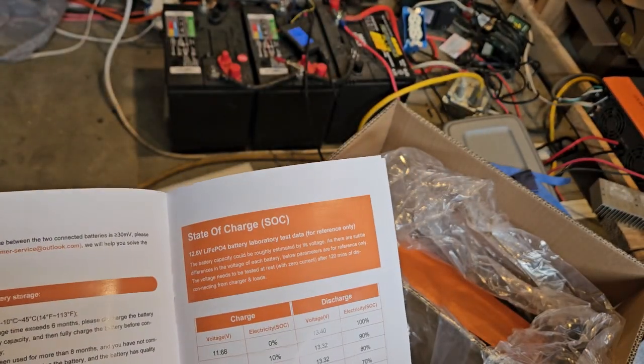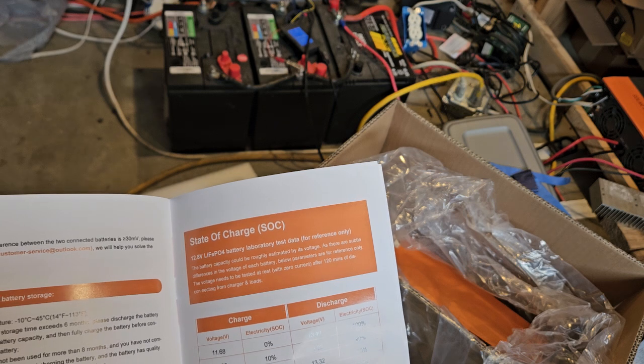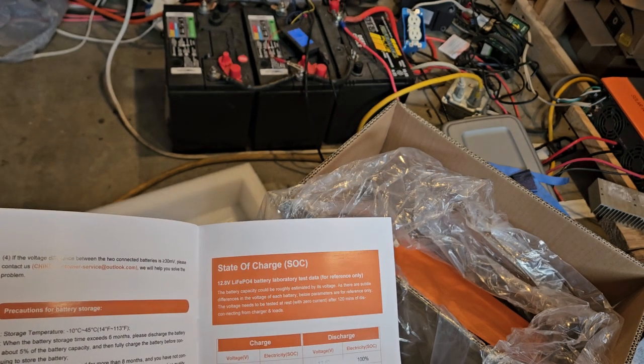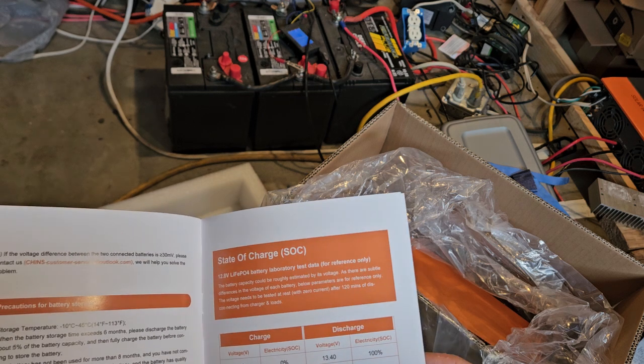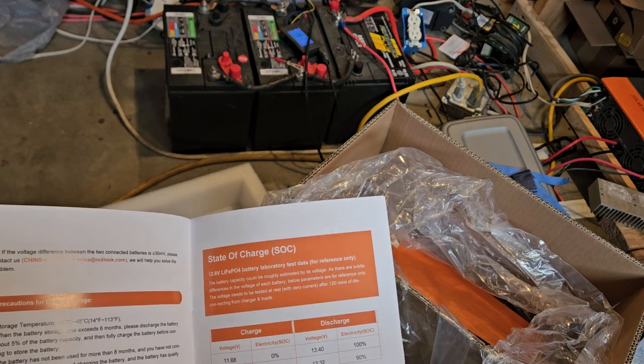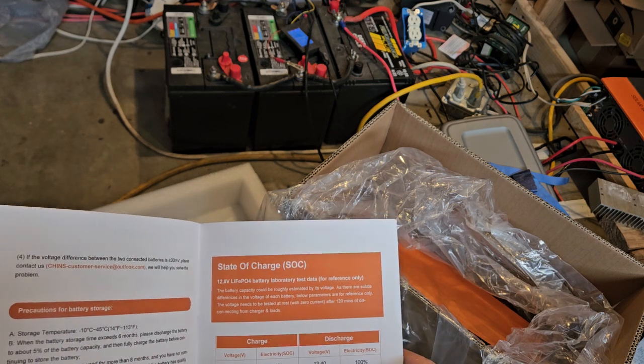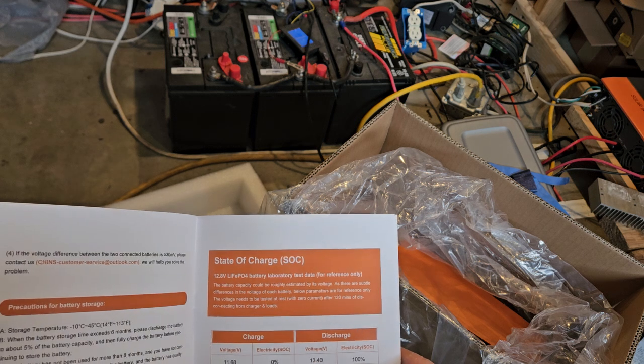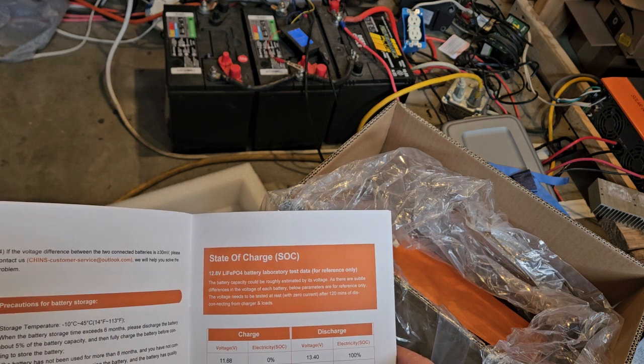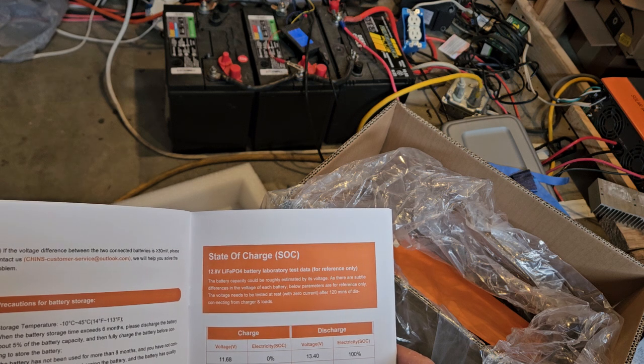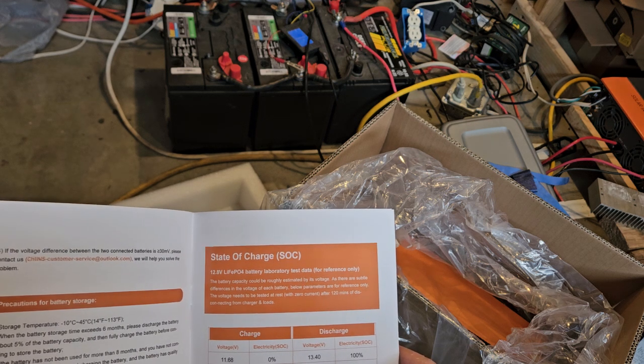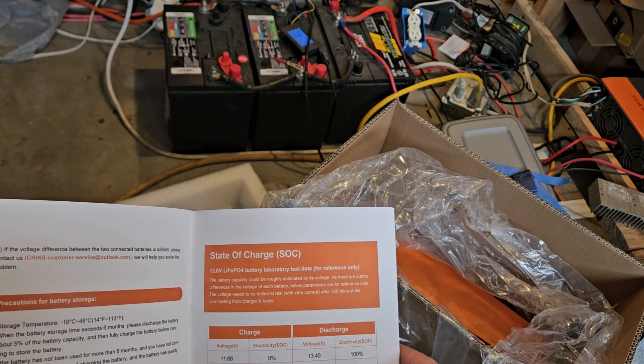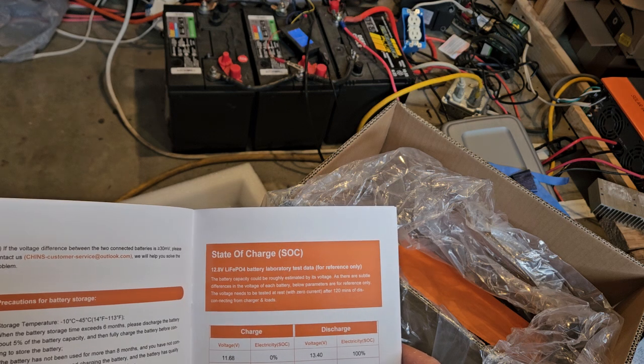Precautions for battery storage. And here's the state of charge chart, which is really nice. So if we look at here, it says 11.68 is where they got the state of charge is 0. So according to this, 12.8 LiFePO4 battery, laboratory test for reference only. The battery capacity could be roughly estimated by its voltage. The differences below the parameters are for reference only. The voltage needs to be tested at rest with 0 current after 120 minutes of disconnecting.